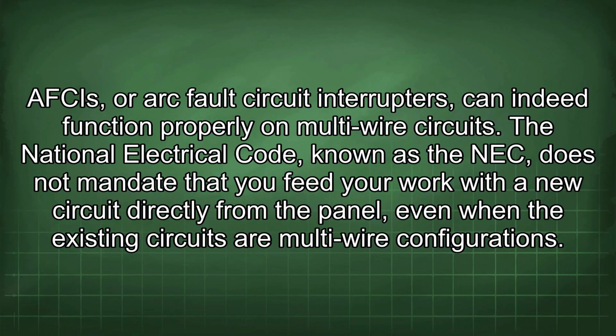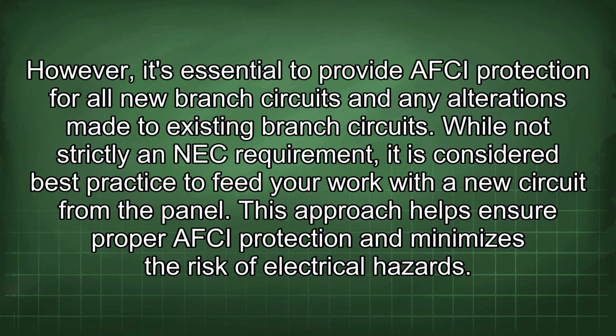AFCIs, or arc fault circuit interrupters, can indeed function properly on multi-wire circuits. The National Electrical Code, known as the NEC, does not mandate that you feed your work with a new circuit directly from the panel, even when the existing circuits are multi-wire configurations. However, it's essential to provide AFCI protection for all new branch circuits and any alterations made to existing branch circuits.